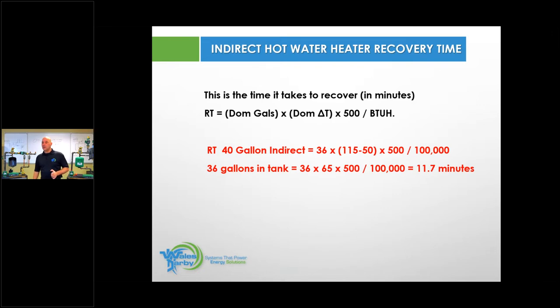Okay, here we have a formula. And this formula right here is going to tell us a lot about hot water. This is recovery time. So this is recovery time based upon what am I trying to heat? What am I trying to heat it with? And what does that look like? Okay, so we have a 40-gallon tank here. And it's an indirect. When you're talking about tanks, whether it's a tank style water heater or an indirect, each manufacturer has to adhere to a certain standard, but usually it's within 80% of advertised number. So here we have a 40-gallon indirect. That 40-gallon indirect holds 36 gallons of water.